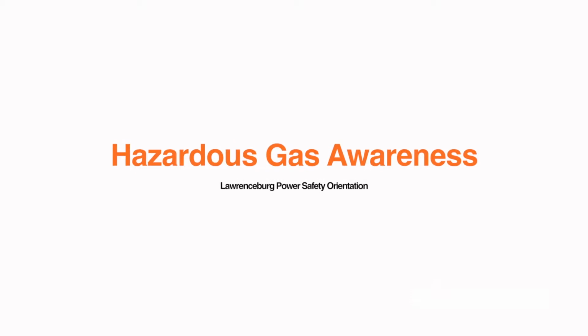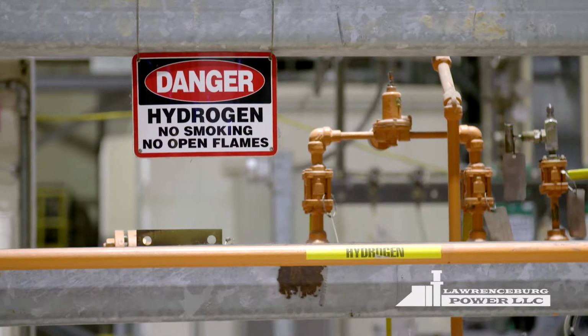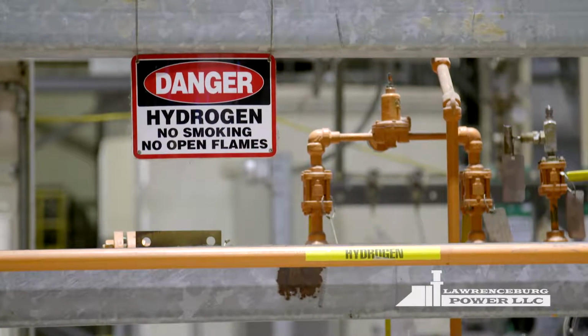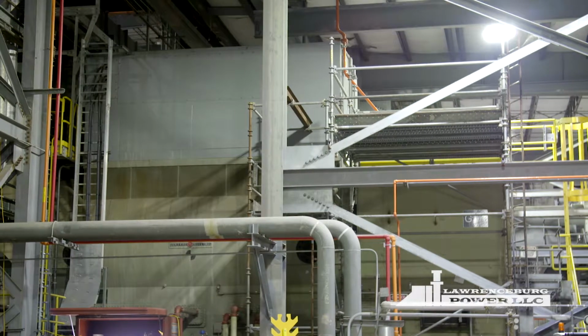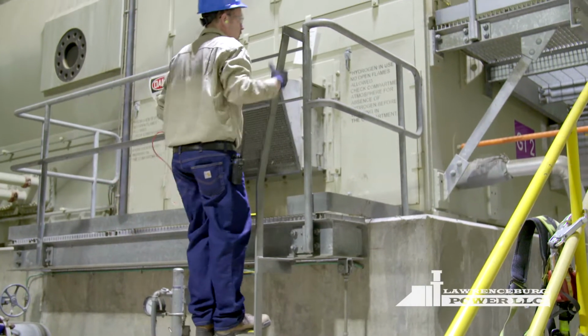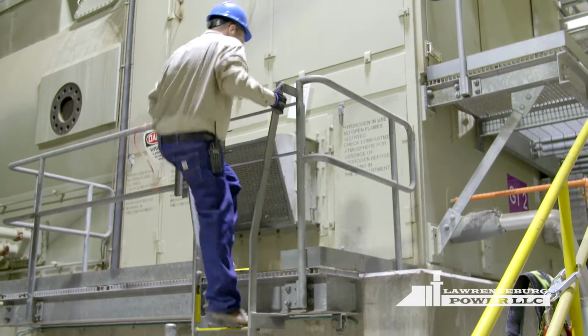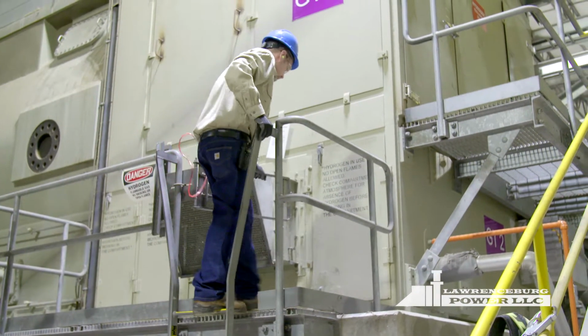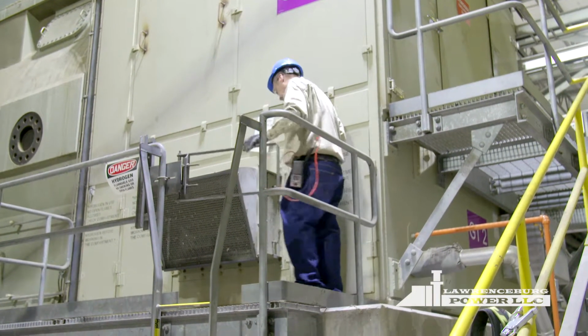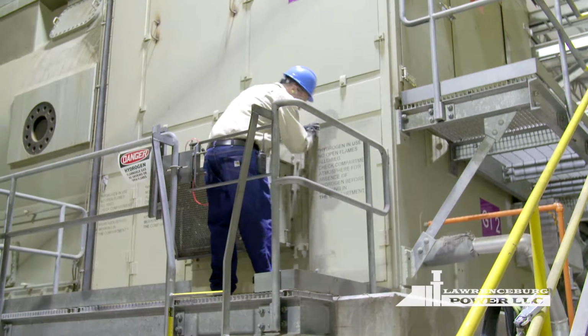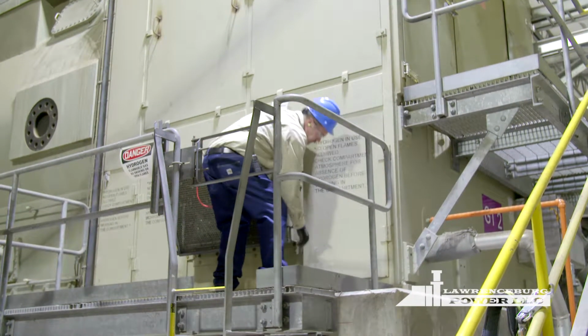Hazardous gas awareness. Natural gas and hydrogen are highly flammable as indicated by the number 4, the highest NFPA flammability rating. The range of flammable mixture for natural gas is between 5% by volume, the lower explosive limit, to 15% by volume, the upper explosive limit.